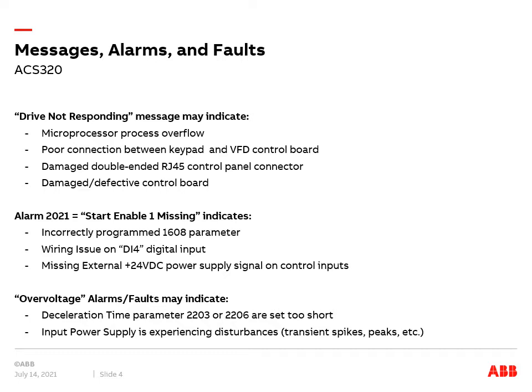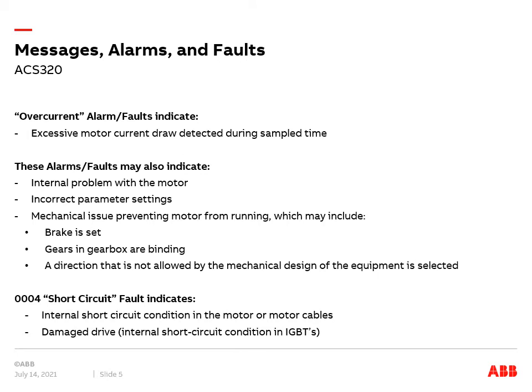Overvoltage alarms or faults are usually indicating input power supply disturbances that are translating over to the DC bus capacitor bank inside the VFD. They can also be caused by the excessive regenerative energy a VFD encounters during too short a deceleration. Overcurrent alarms and faults indicate excessive motor current draw.